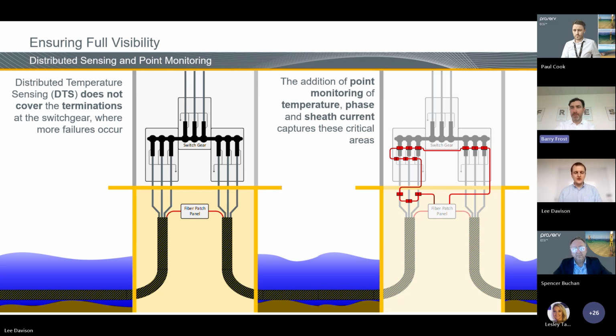Physically, the temperature sensors come in different forms, but essentially they're quite small, smaller than a biro really, and just spliced into the fiber optic system. The current measurements use a standard industry-standard current transformer - typically a split core one, so we can retrofit around existing cables without needing to touch, demate, or mate any HV connections. We clamp around them, and the secondary winding from those CTs goes to a passive secondary converter that converts the electrical signal into the optical system, which is then spliced in.